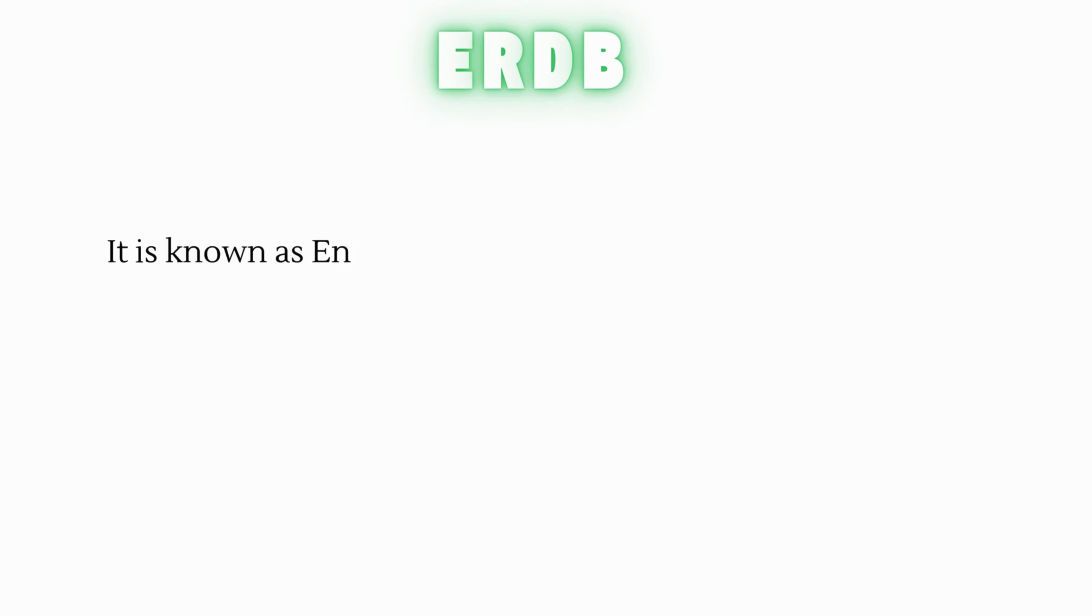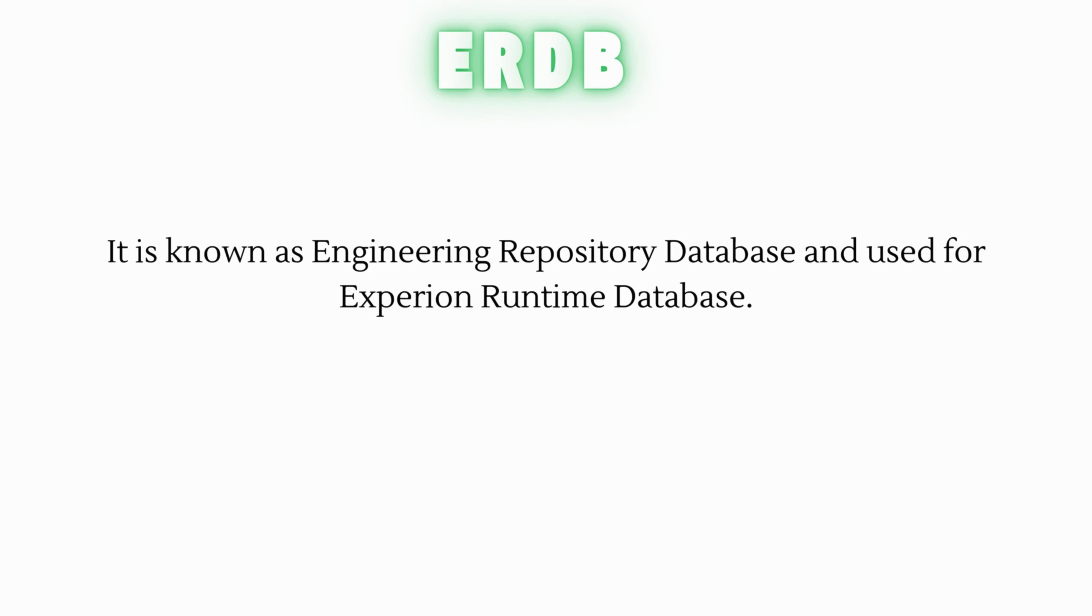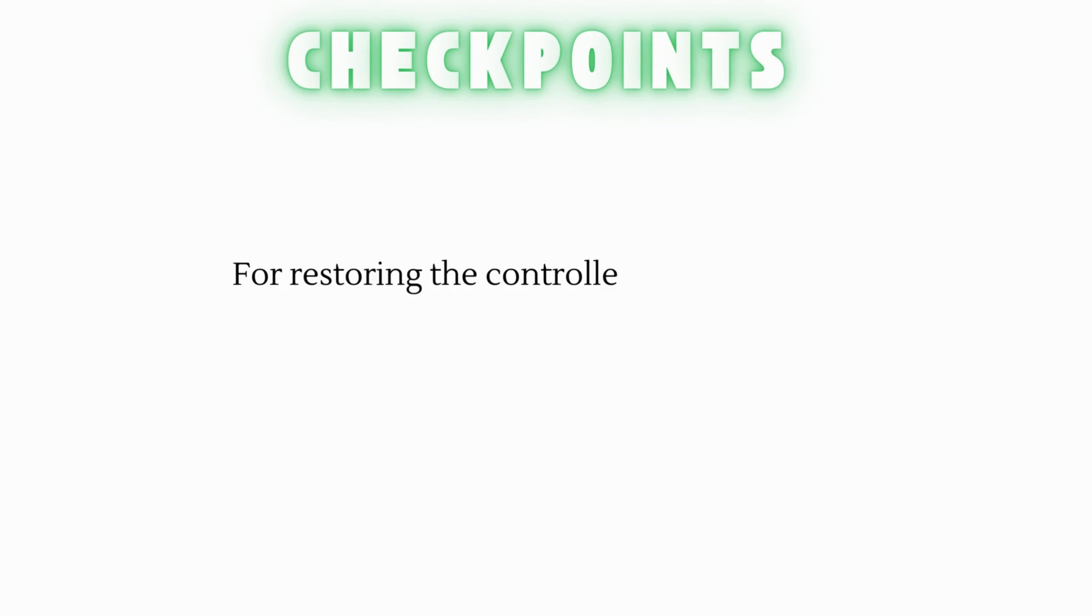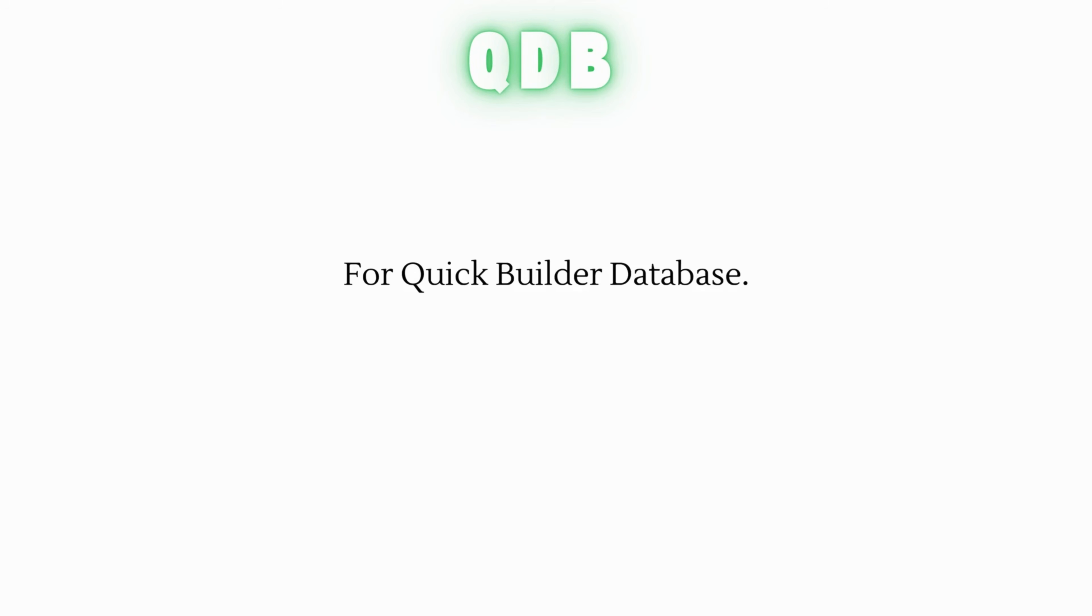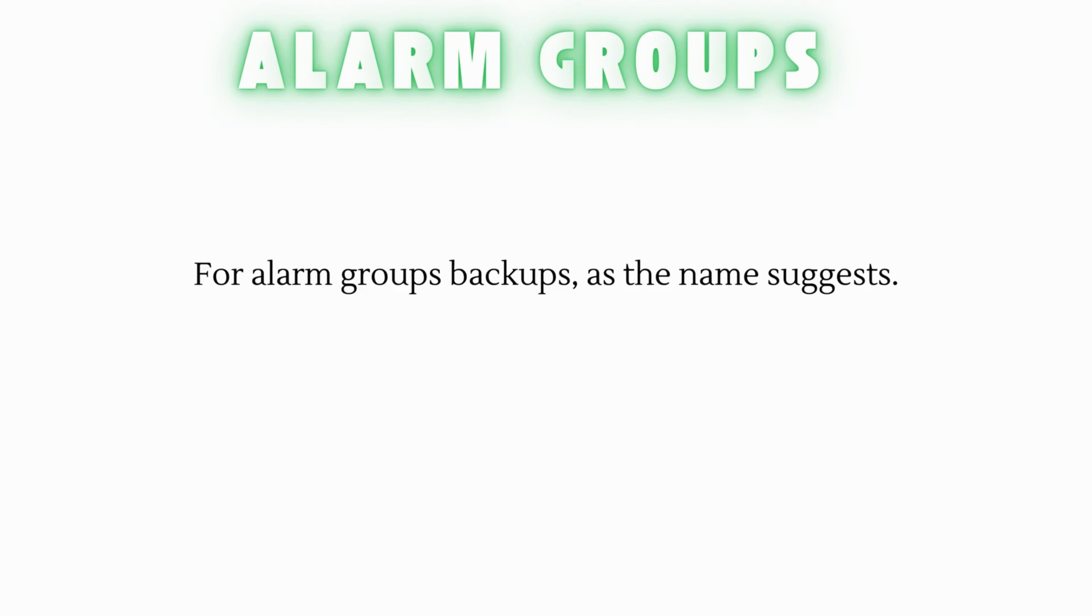ERDB Backup. It is known as Engineering Repository Database and used for Experion Runtime Database. Checkpoint and Checkpoint Database for restoring the controller configurations. QDB Backup for Quick Builder Database. Alarm Groups Backup for Alarm Groups Backups as the name suggests.